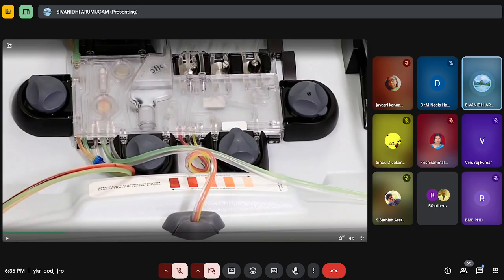And I mentioned valves. So these are called valves. This is called the RBC valve, and this is for plasma, this is for platelet. Now you can see there are two tubes in between the valves, right? One is for processing, one is for collecting. Once the centrifuge has separated the components, if I'm collecting it, I just want to block this tube. Otherwise, due to gravity, the collected component will go back to the container. So to prevent that, we have this valve. Once we have collected, the valve will close that tube. So it won't let the RBC or plasma or platelets fall back again to the container.